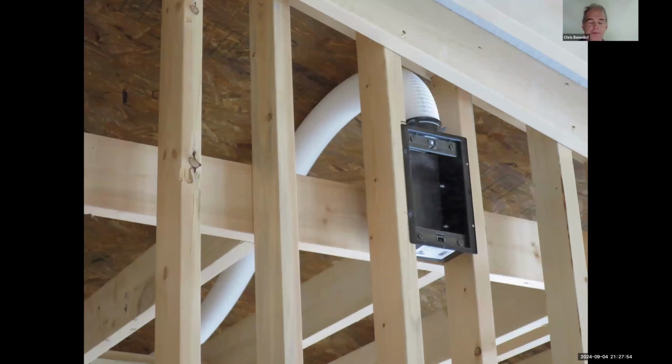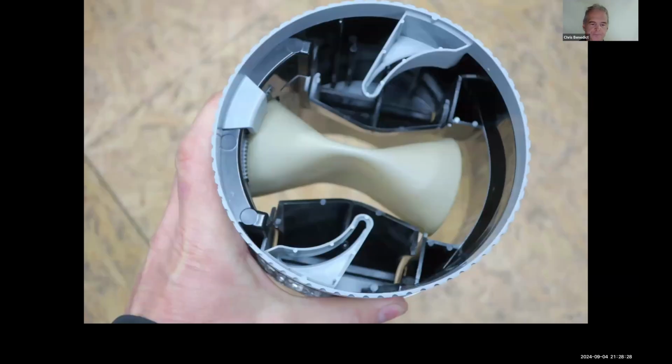This is a system with vacuum cleaner hoses. They don't call it that, but it's basically vacuum cleaner hoses with a pretty smooth inside to improve airflow, and it just has a snap connection to boxes. They have mufflers, tees, distribution boxes. All this is what's common in Europe. The hoses fit in a 2x4 wall. One hose is maybe not enough for a bedroom, so you put 2 hoses, and it really saves on labor. And they charge for this stuff. We don't use it much in New York City because it's not UL approved yet, I don't think, last I heard. But this is a nice way to do a ventilation system.